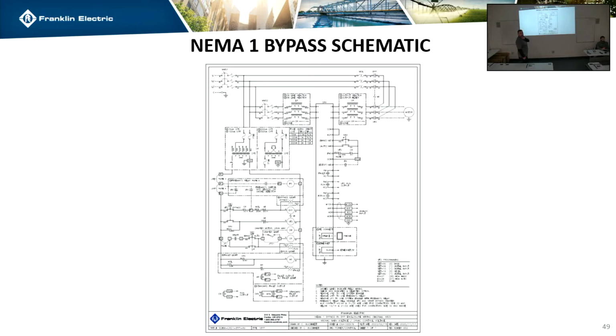You guys understand that? If you're working on a drive, a 2 contactor bypass does not isolate the drive from power. Essentially, this would be gone. And so you'd always have power to the bypass and the VFD. And what we're talking about is the reason that this is cool is if the VFD goes down, our VFD is not tied to the bypass controls. It's separate. So if the VFD goes out, turn the MMS off, you can physically remove the drive and run it in bypass and there's no problem. You're fine. So you can do replacements or troubleshooting and all that kind of stuff.